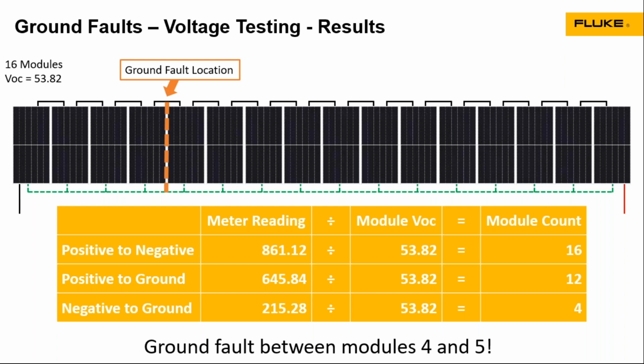So now I need to go figure out where this string is, go out into the field, and figure out where the 4th and 5th modules from the negative side are. I would do a visual inspection and see if I can find the ground fault.